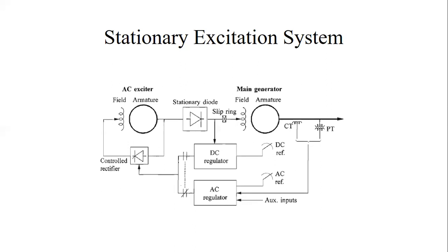The voltage regulator controls the firing of the thyristor. The exciter alternator is self-excited and uses an independent static voltage regulator to maintain its output voltage. Since the thyristors directly control the exciter output, this system inherently provides high initial response, that is, small response time.